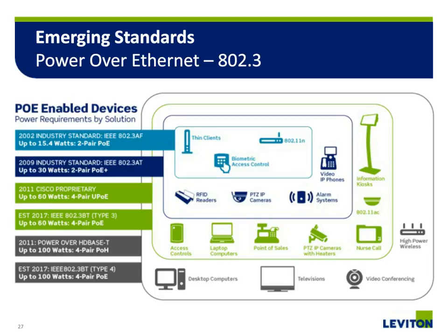But what we have found is IEEE recognized the need, and they're working on a draft right now, 802.3bt, which will eventually replace 802.3at. And that standard is going to recognize four types of powered devices. Type 1, 15.4. Type 2 is 30 watts. Type 3 will be the 60 watts using all four pairs, and that's going to mimic what Cisco had. And then the big news right now is Type 4, which is 100 watts of power over the four-pair PoE.